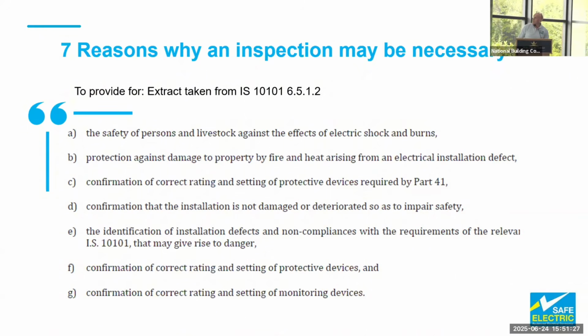Confirmation that the installation is not damaged or deteriorated so as to impair safety. The identification of the installation defects and non-compliances with the requirements of the relevant wiring rules that may give rise to danger. Confirmation of correct rating and setting of protective devices, and confirmation of correct rating and setting of monitoring devices.